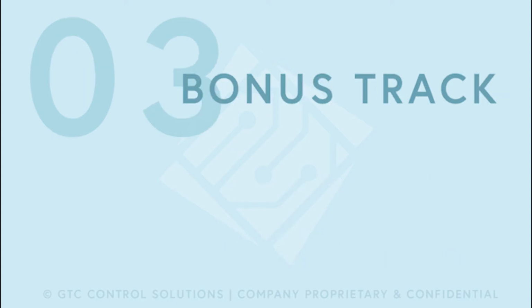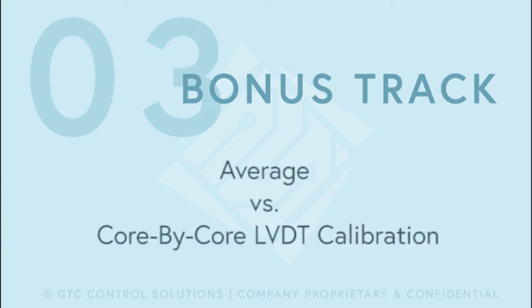As a bonus track, we will discuss very shortly the difference between average versus core-by-core LVDT calibration. The Mark 6 and the Mark 6E went back to the Mark 4 style of calibration, doing it core-by-core by themselves. The Mark 5 does not do that. So that's the Mark 5 that requires special attention.